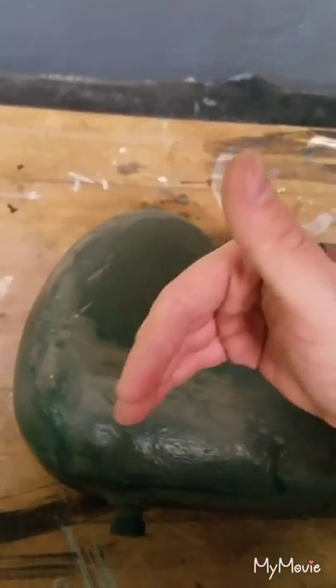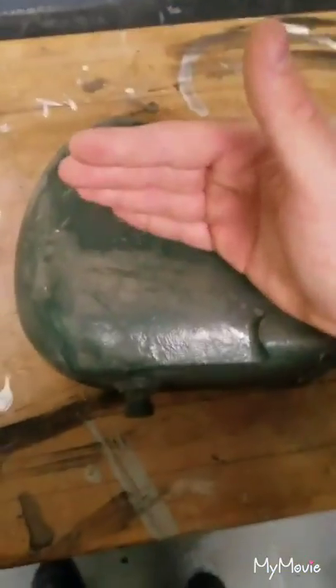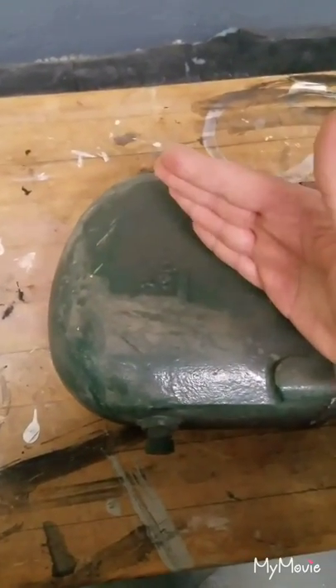The way it works is there's a ball in here, and it floats. So when the steam comes in, the ball's down. The steam comes in, the condensate lifts the ball up, and the condensate comes back out here. When the ball lifts up enough and most of the condensate goes out, it comes back down, steam comes in, lifts back up, and condensate comes out. So that's how that ball lift steam trap works.